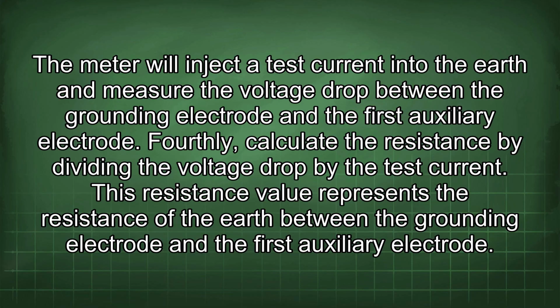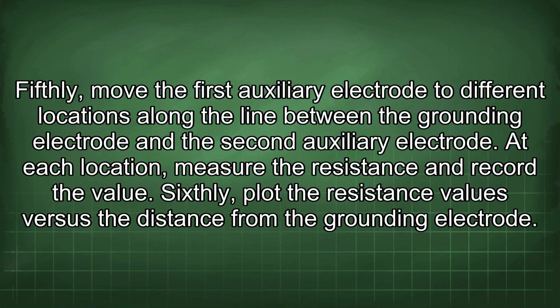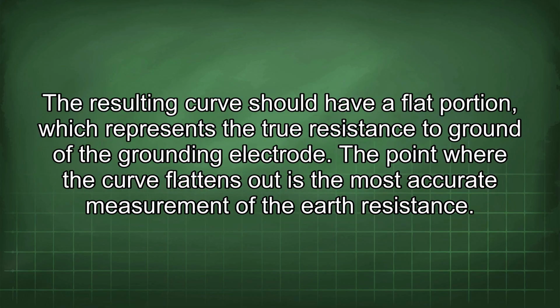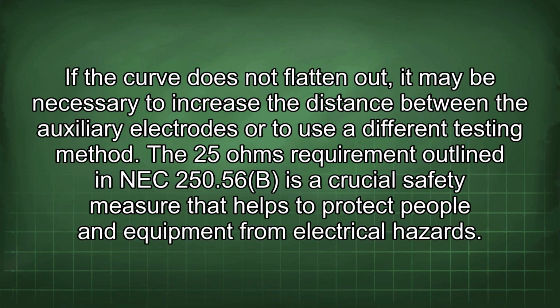This resistance value represents the resistance of the earth between the grounding electrode and the first auxiliary electrode. Fifthly, move the first auxiliary electrode to different locations along the line between the grounding electrode and the second auxiliary electrode. At each location, measure the resistance and record the value. Sixthly, plot the resistance values versus the distance from the grounding electrode. The resulting curve should have a flat portion, which represents the true resistance to ground of the grounding electrode. The point where the curve flattens out is the most accurate measurement of the earth resistance. If the curve does not flatten out, it may be necessary to increase the distance between the auxiliary electrodes or to use a different testing method.